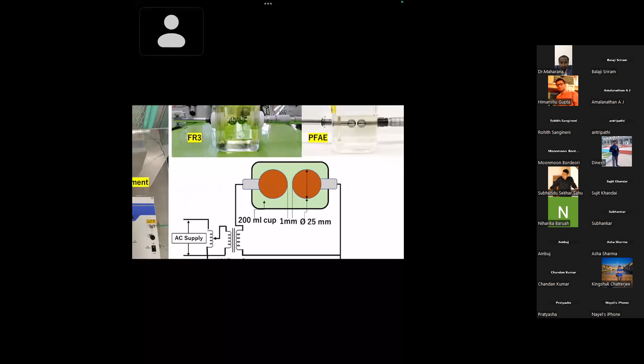Generally, people across the globe follow the standard of ASTM D1816, but it can go up to like 50, 60, 70 or 100 kV, but there is a rating problem in the transformer, so a maximum of 50 kV is available. So the gap distance was decreased to 1 mm, and we measured the AC breakdown voltage of the oil. So what interesting thing we observe here, as you can see in the left part of the graph, we are measuring the AC breakdown voltage.